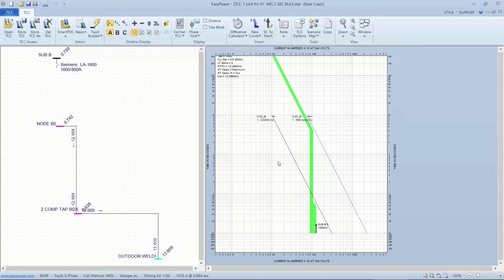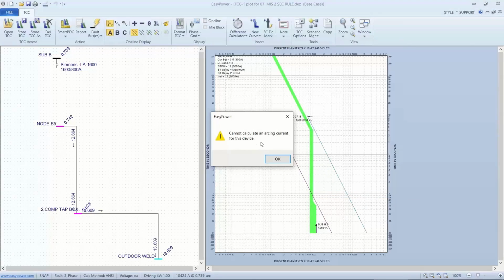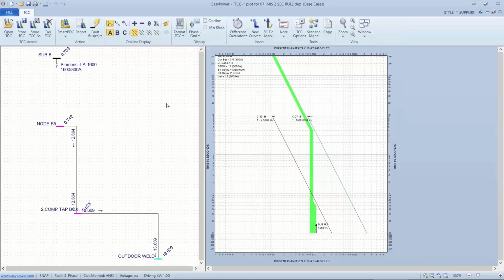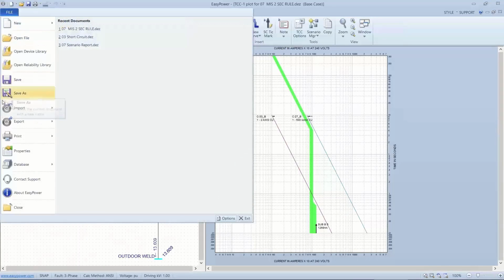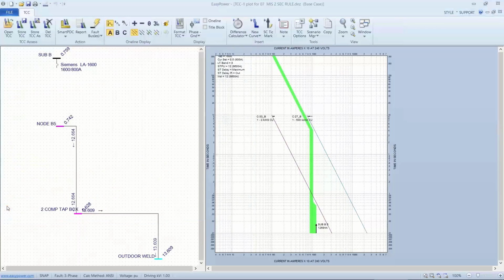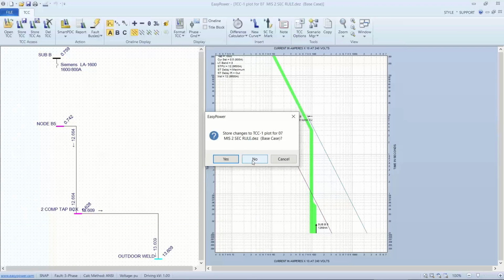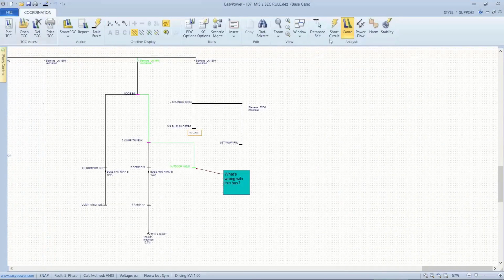Now, it can't give me an answer. I don't know if you read that result. If I insert the arcing tick mark, it says it can't calculate the arcing current for this device. And the reason for that is we're tripping on a fixed time. The device itself is not controlling the time. So let's go back and fix it. Let's close this. Let's not worry about saving changes just yet.